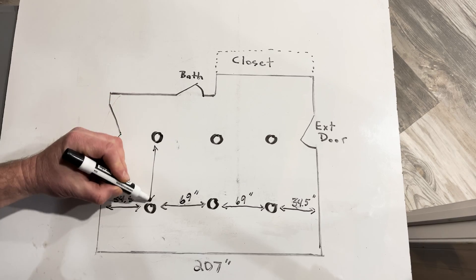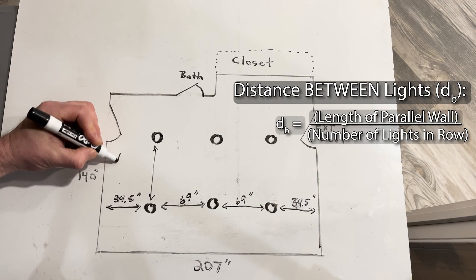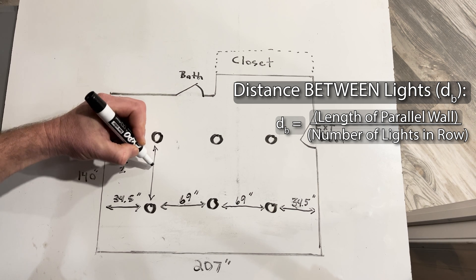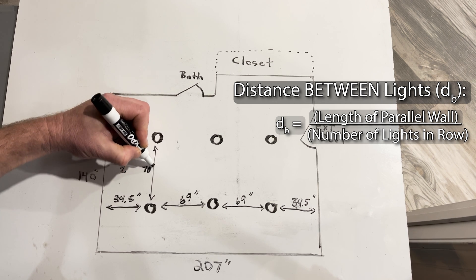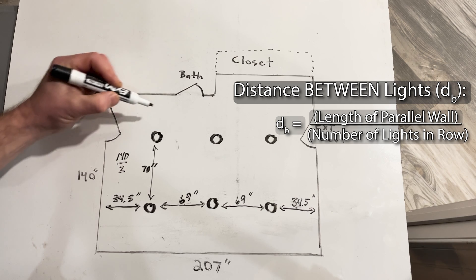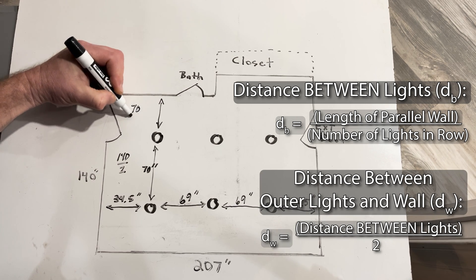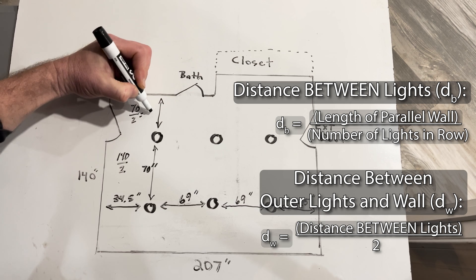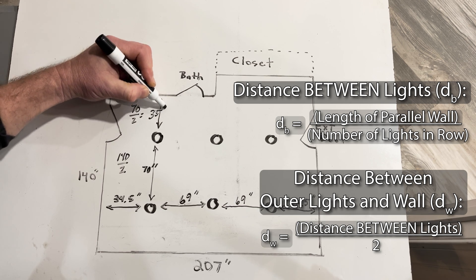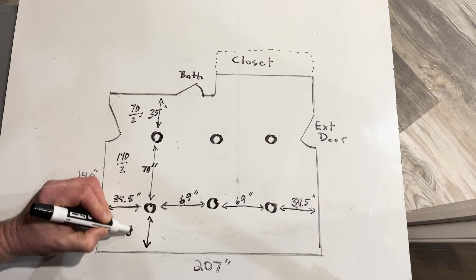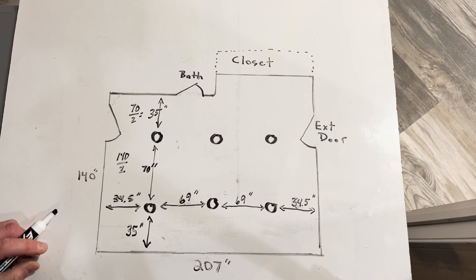The same approach works for the other wall as well. I'll take the wall length, 140 inches, divide by the number of lights, which in this case is two, and this gives me 70 inches. So there will be 70 inches between the lights. Then divide 70 inches by two to determine the distance between the lights and the walls. 70 divided by two is 35.